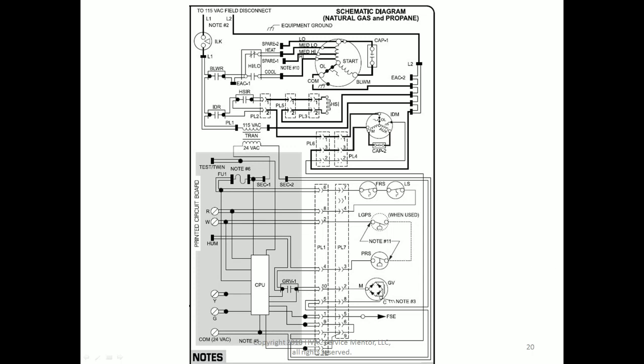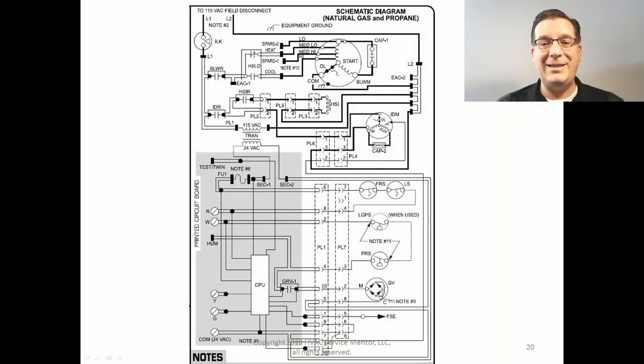This is the first example we have of a voltage send and return right here. Boom, voltage send, 24 volts out, through the limit switches, which are normally closed. Voltage return, 24 volts back. And you see that little dot right there? See how that takes off of that voltage and comes back to the central processing unit? This is how the board knows that those switches are closed.